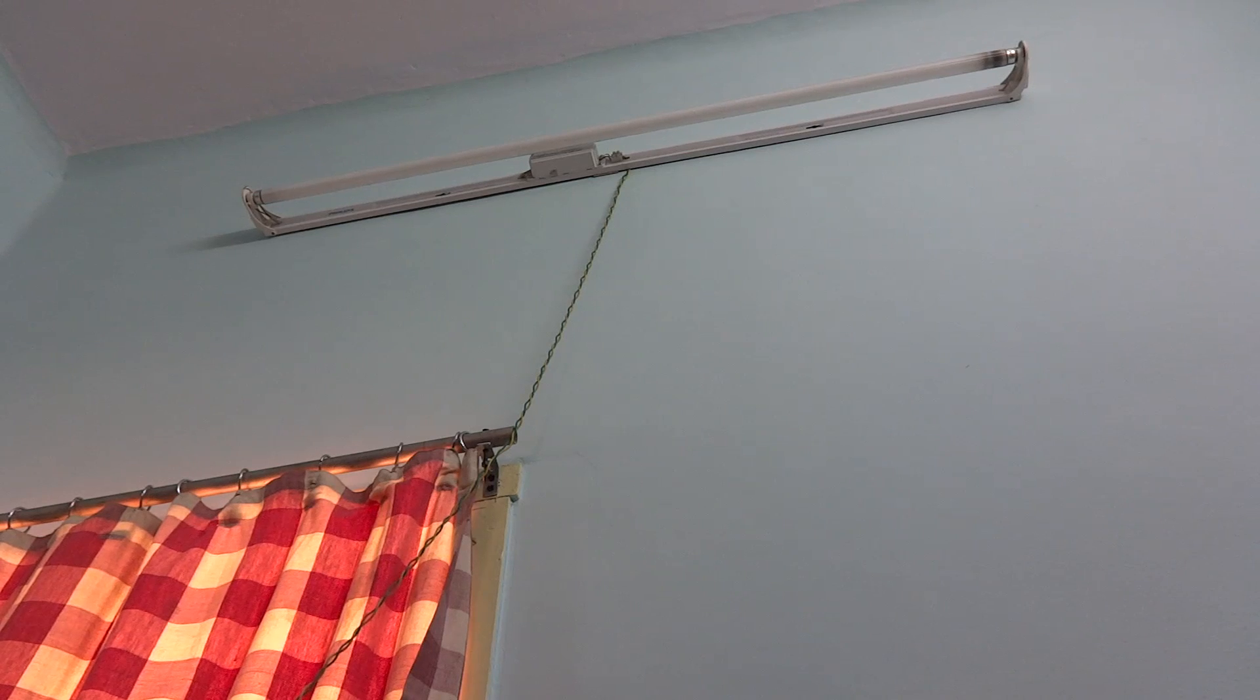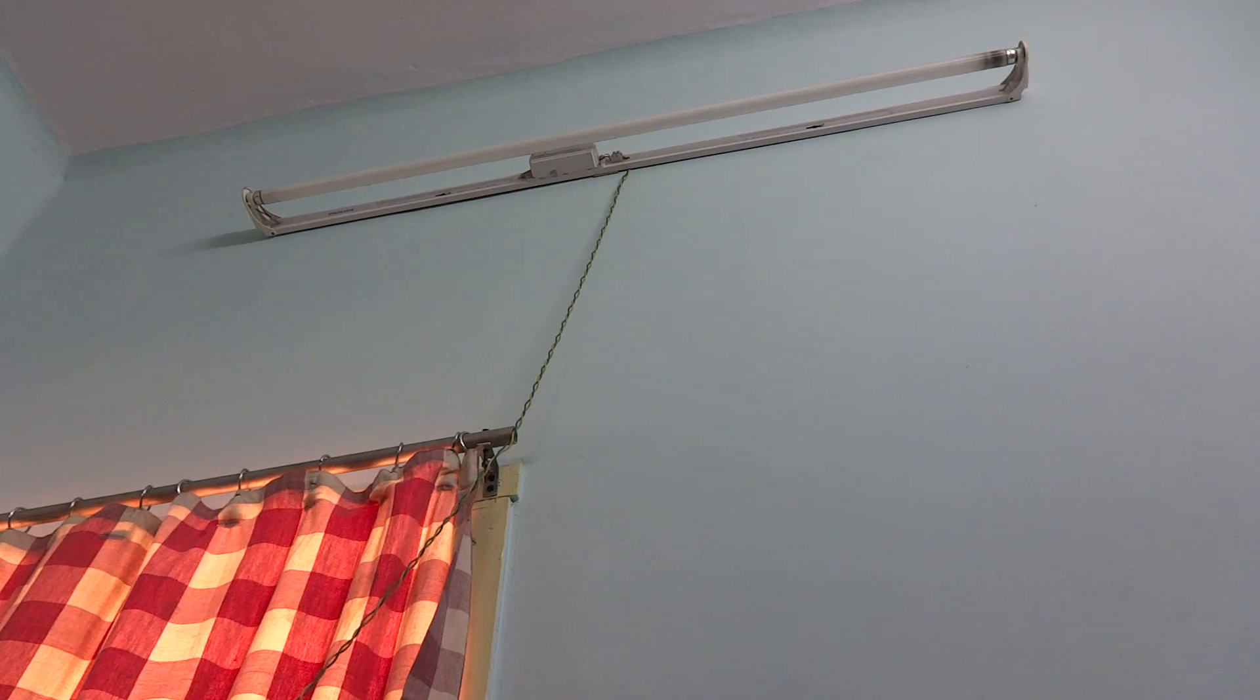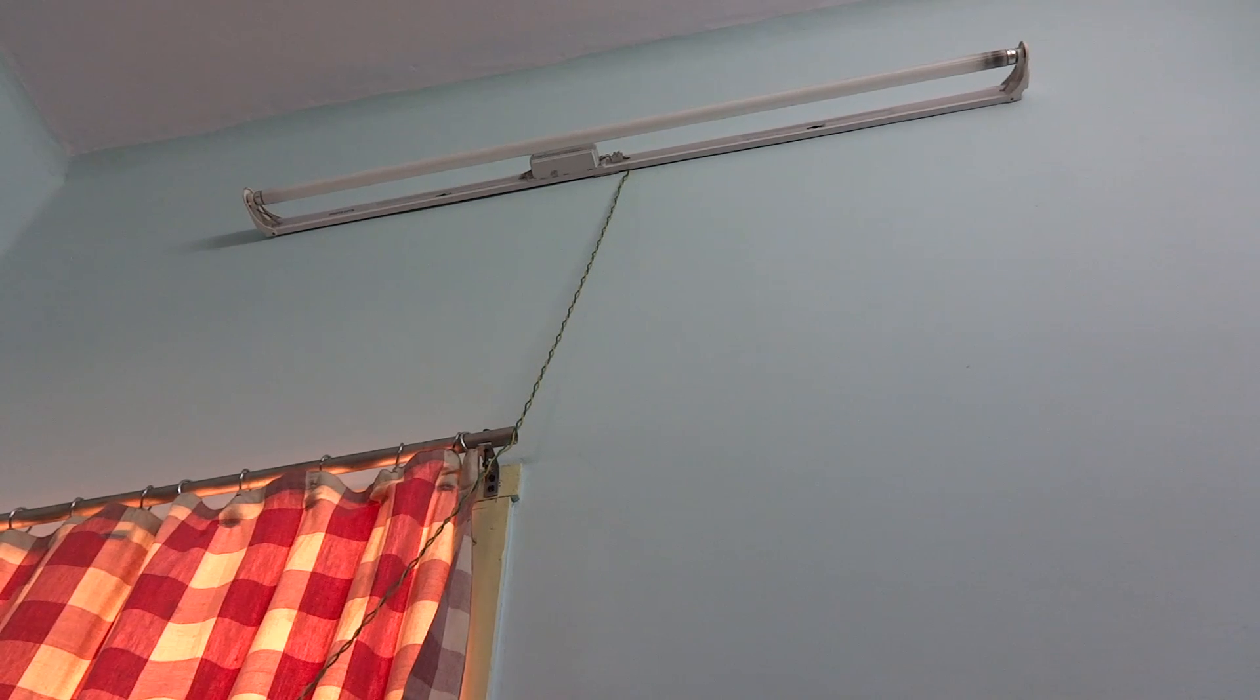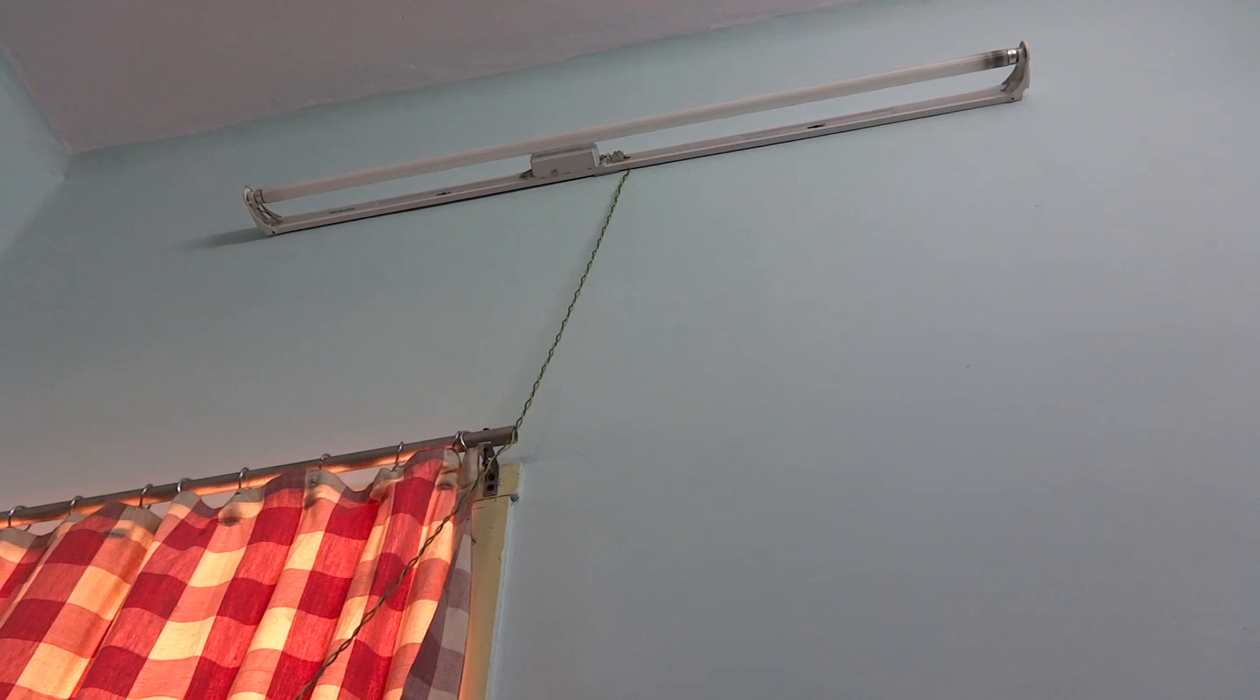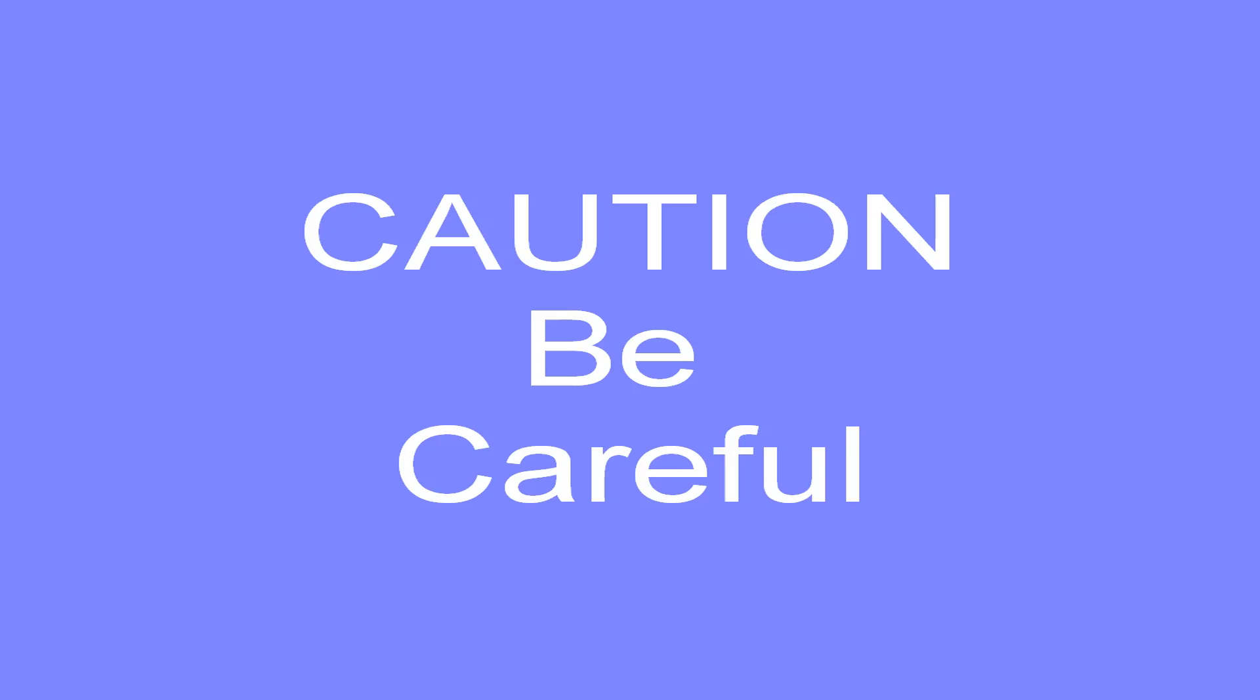It is not recommended to short out both ends as this would lead to failure of the electronic ballast. Kindly use this method with care as the electronic ballast generates very high voltages.